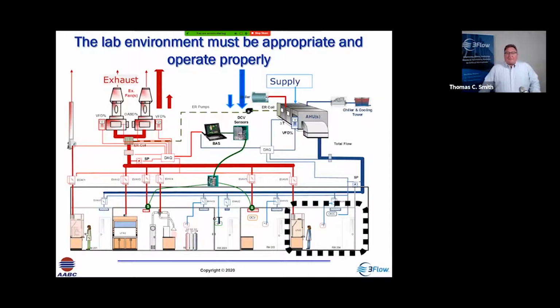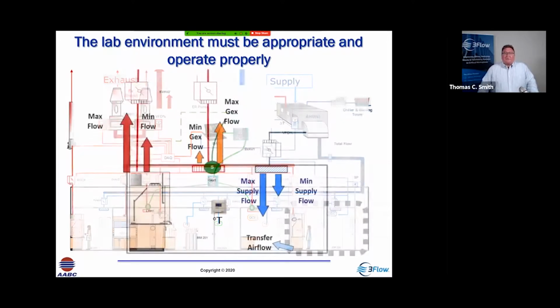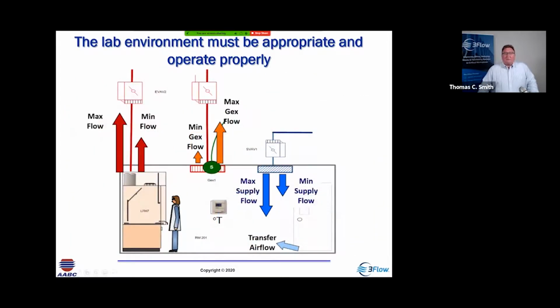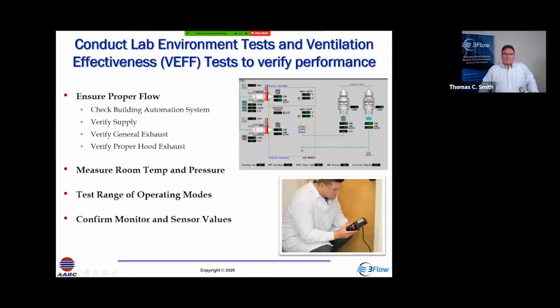So in the lab environment, the lab is to support the hood. And so when we look at the overall flow, we need to make sure that in order for the hood to function properly, we've got to have the right air balance, the right room pressurization, the right supply, and it has to match the exhaust. And so they're working in tandem. So as the exhaust increases to the hood, the supply has to increase. As temperature changes, general exhaust is going to increase. All of these factors are associated and related. And so in order for it to work properly, we have to make sure the whole space is balanced. So we can conduct ventilation measurements.